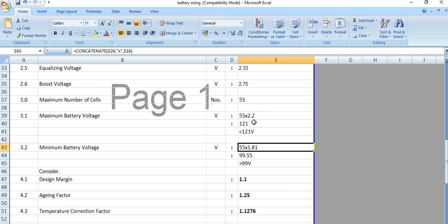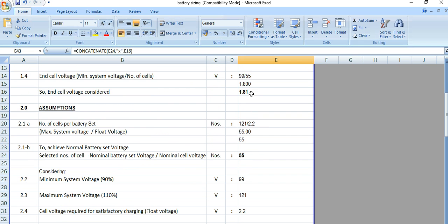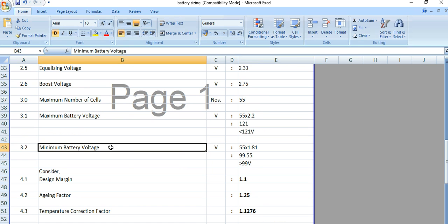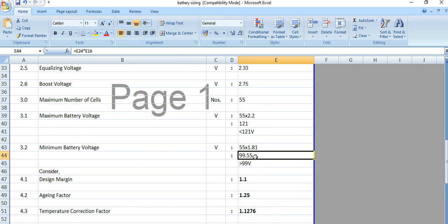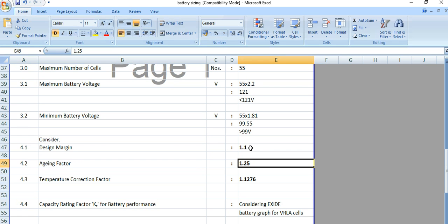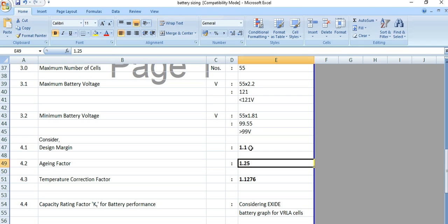Minimum battery voltage is 55 multiplied by 1.81 (E16, the end cell voltage), which comes to 99.5 volts. We have considered a design margin of 1.1 (10%) and an aging factor of 1.25 (25%).